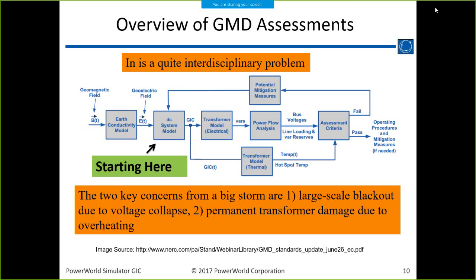The block diagram starts with a magnetic field B sub T there. You have an earth conductivity model that produces an electric field. The electric field, you use a DC model of the system, and that lets you calculate the GICs. The GICs then go into the transformer model, which produces changes in reactive power. That can go into power flow analysis, and that gets you changes in bus voltages, line loadings, and var reserves, stuff like that.